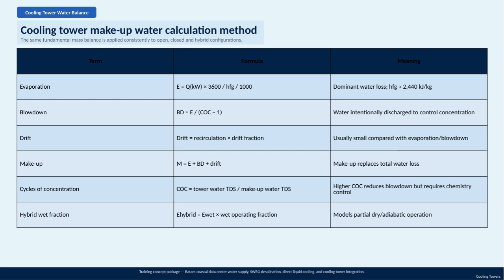Cycles of concentration, or COC, express the ratio of total dissolved solids in the tower water to those in the makeup water. Increasing the COC reduces the blowdown rate, but requires careful water chemistry control to avoid scaling or corrosion. Lastly, the hybrid wet fraction accounts for partial dry or adiabatic operation in hybrid cooling towers. This is modeled by multiplying the wet evaporation rate by the fraction of time the wet mode is active.